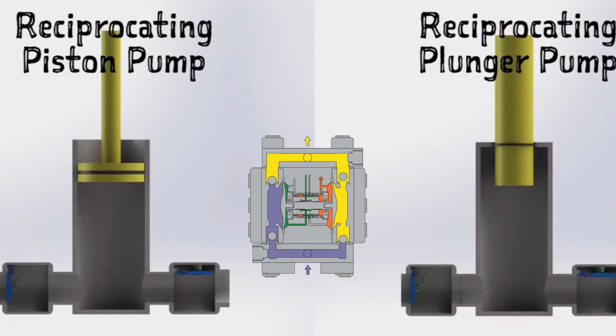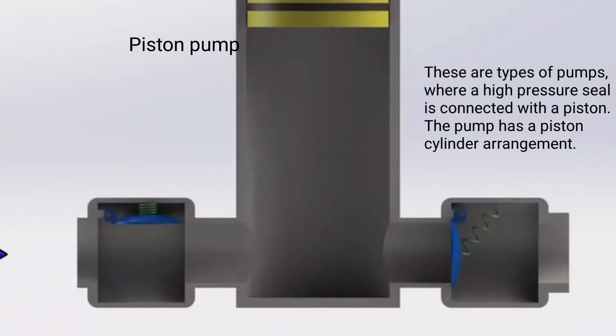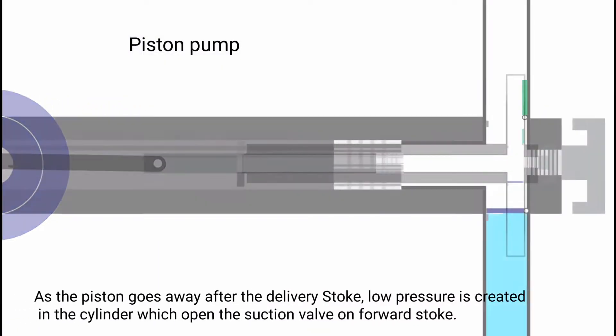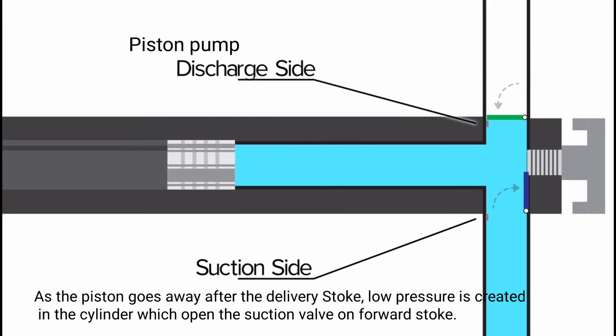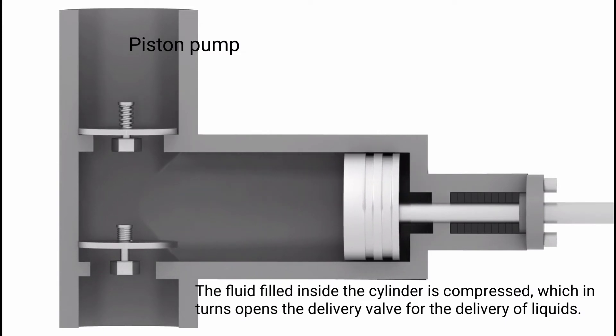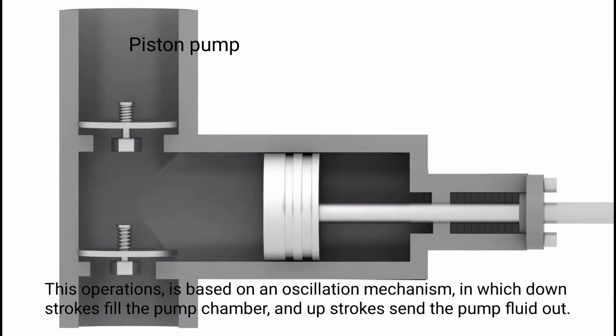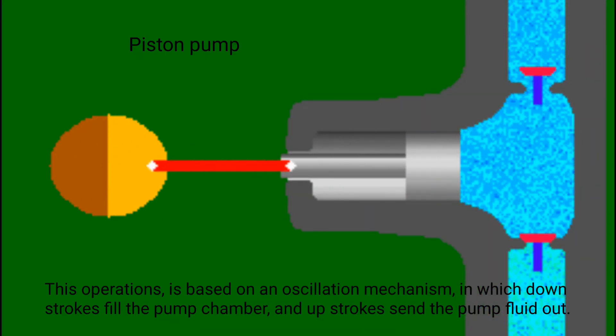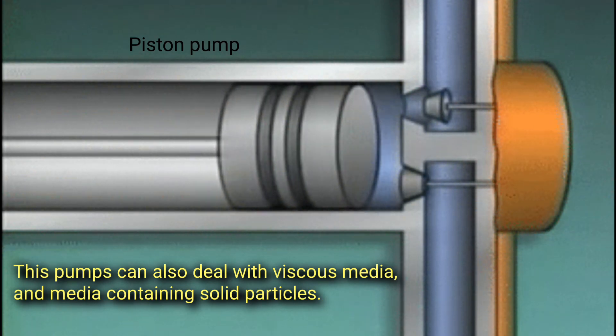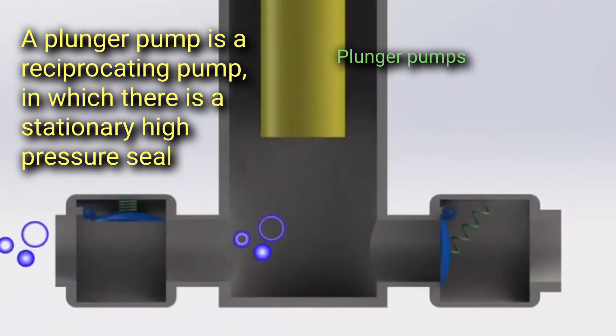Piston pumps are types of pumps where a high-pressure seal is connected with a piston. The pump has a piston-cylinder arrangement. As the piston retracts after the delivery stroke, low pressure is created in the cylinder, which opens the suction valve. On the forward stroke, the fluid filled inside the cylinder is compressed, which opens the delivery valve for the delivery of liquids. This operation is based on an oscillation mechanism in which down-strokes fill the pump chamber and up-strokes send the fluid out. These pumps can also handle viscous media and media containing solid particles.